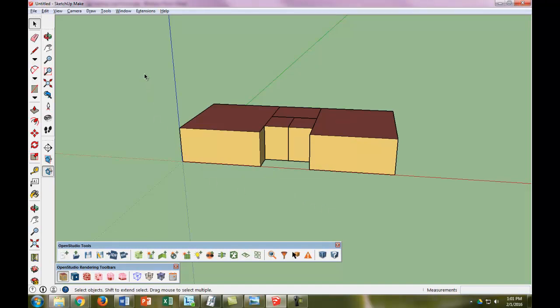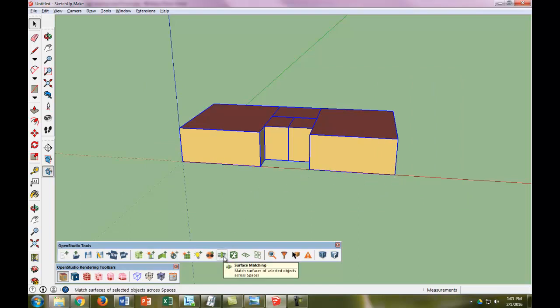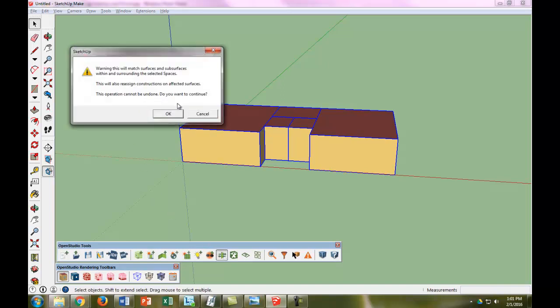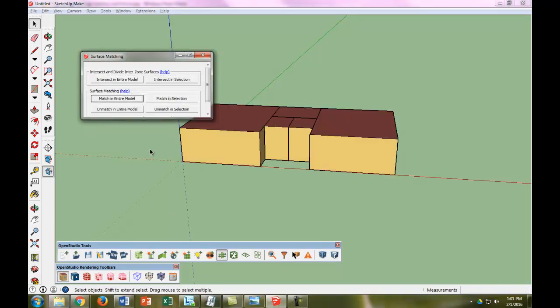So now the next step is we're going to select our whole model and do something called Surface Matching. What Surface Matching does is it makes sure that all the outside walls are treated as outside walls in OpenStudio and EnergyPlus, and that all of the inside walls are treated as such, and all the floors that are touching the ground are treated as ground surfaces. So let's go ahead and click Match in Entire Model.